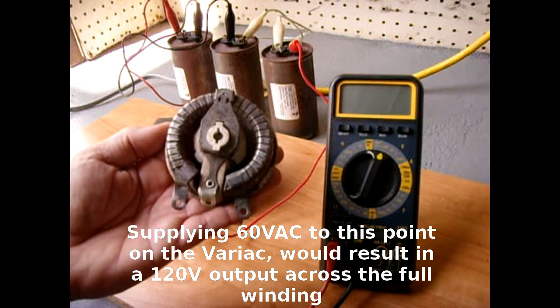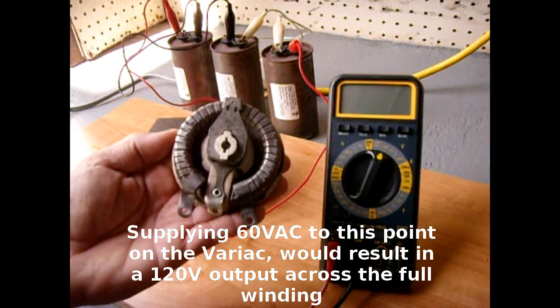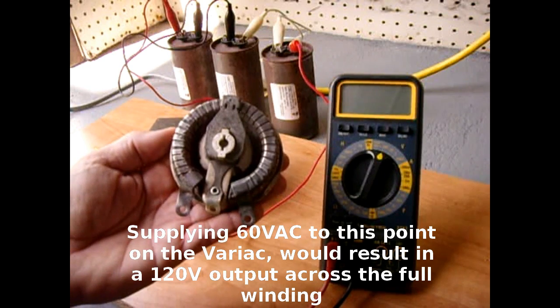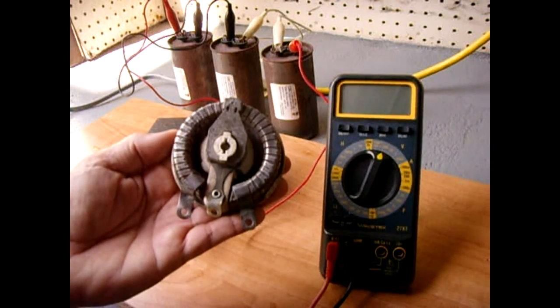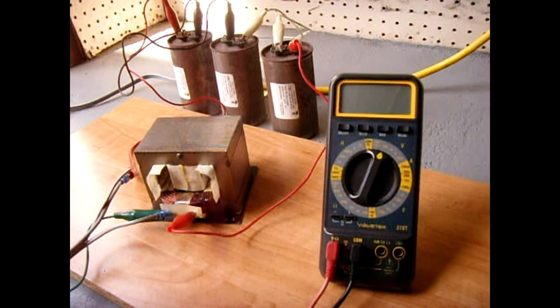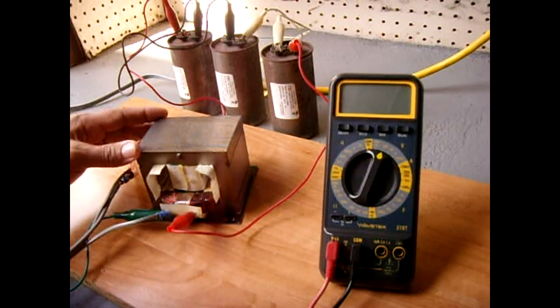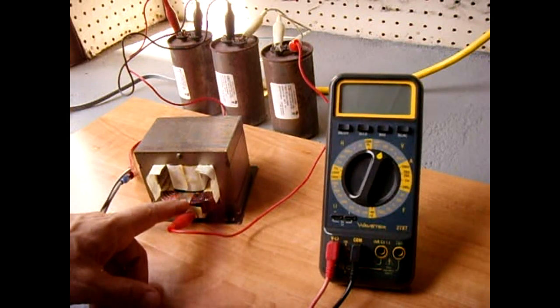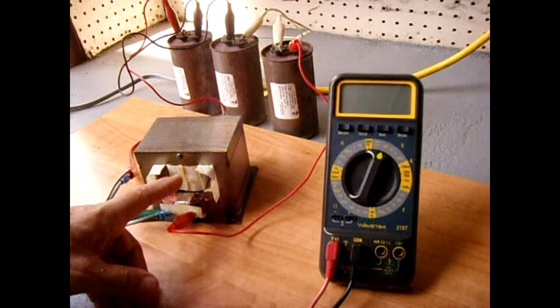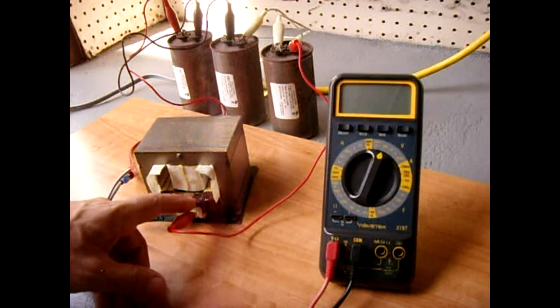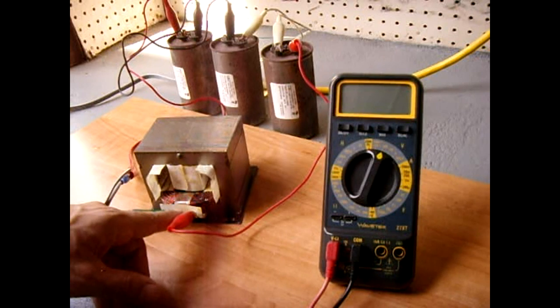Now they make variacs step up and step down, but the most common ones are used for stepping down. Now the only issue you have when using an auto transformer or a variac is that you do not have any isolation between your primary winding and secondary winding. All the power is being tapped off of the single winding you see here.